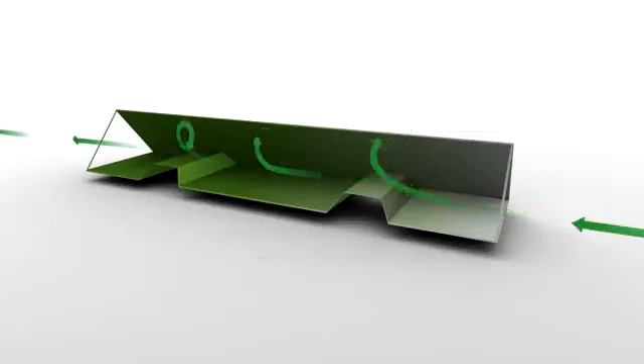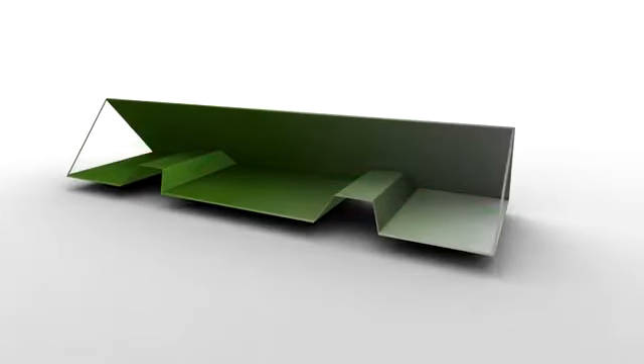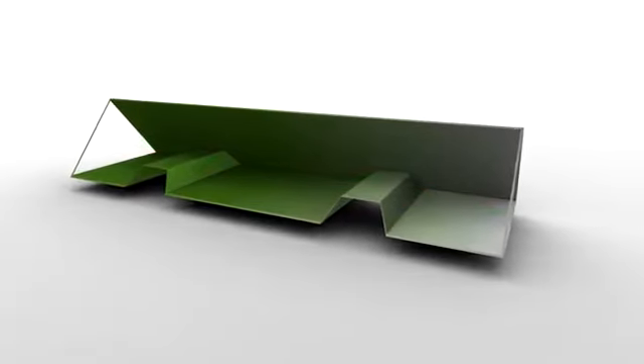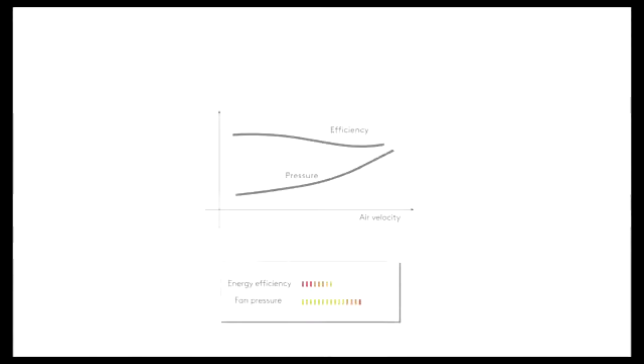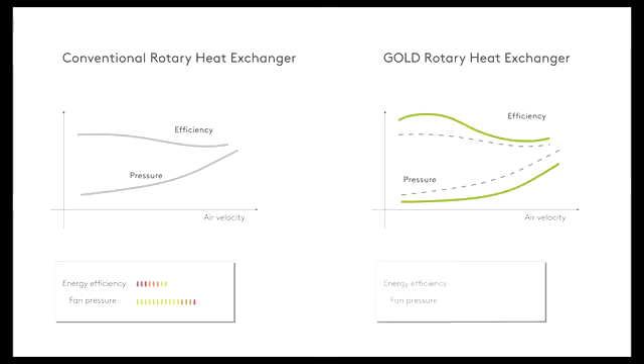Thanks to the increased efficiency, each air channel can be made slightly larger, which reduces the pressure drop and saves fan energy. Compared to the conventional rotor, the Gold rotor has higher efficiency with less pressure drop, allowing for increased recuperation and lowering of fan energy consumption. Doubled profit for you, doubled profit for the environment.